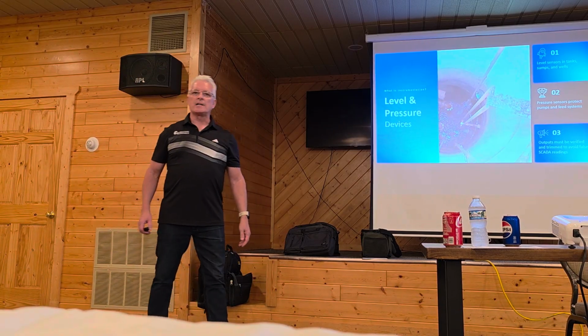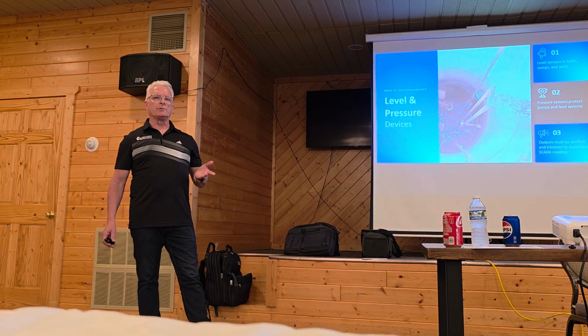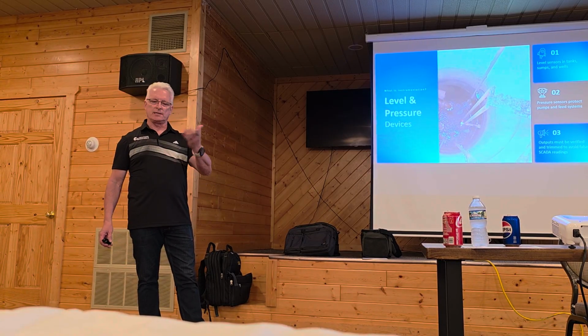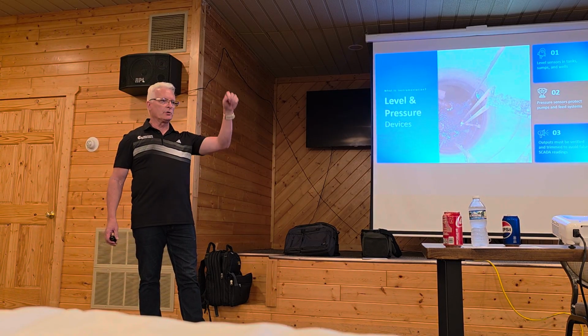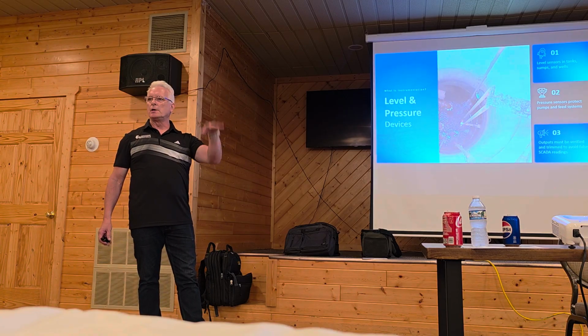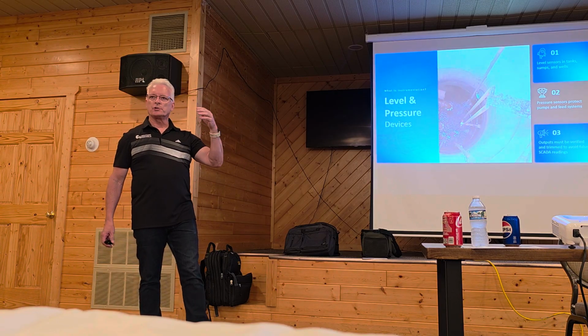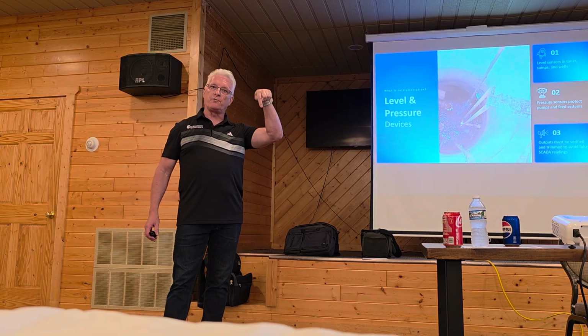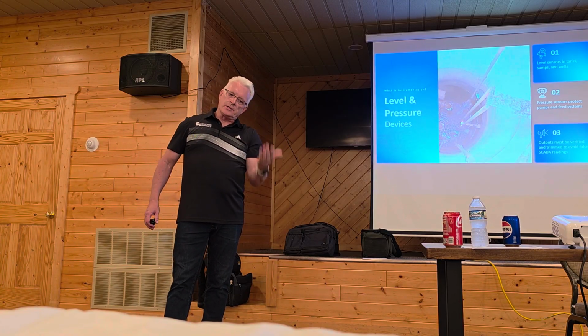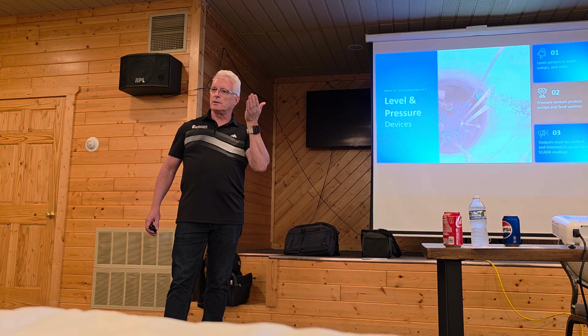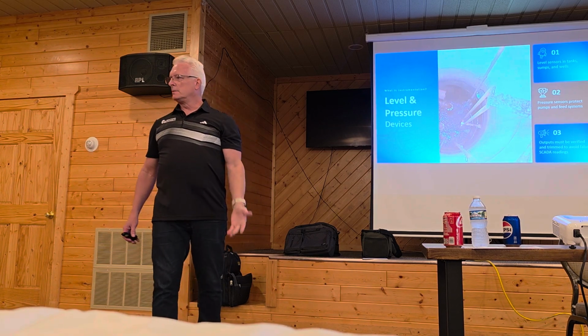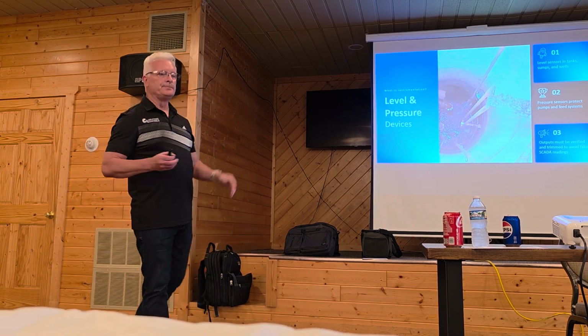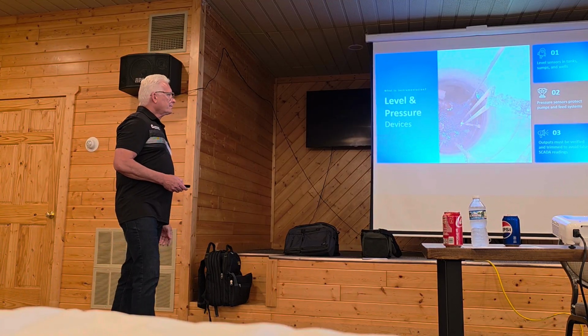You can also use ultrasonic. Lately I've been seeing more pressure than I see ultrasonic because they can sometimes get a film on them and stuff. But ultrasonic can also read down and tells you how high the water is. So ultrasonic can do two things. It can read down and tell you how far it is away, or you can reverse it and have it set to 0 at the very bottom, and then you can tell it how high the water is in the device or whatever product it is.